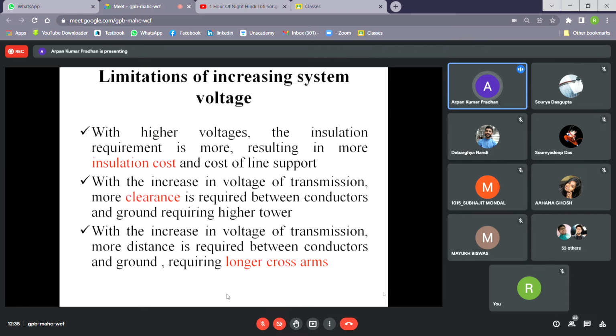While you are transmitting the power at very high voltages, your requirement of insulation will also increase, because the design of the insulation does not depend on the current but on the voltage. As your voltage level increases, so does the insulation cost of the terminal equipment. For example, at the generating station you generate the power at 11 kV and transmit at a much higher voltage, so you require a step-up transformer, and the insulation cost for that transformer will increase, which may increase the overall cost of the system. This is one main disadvantage.